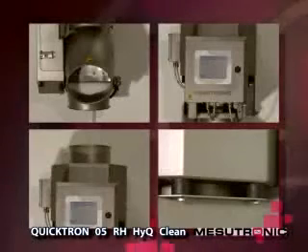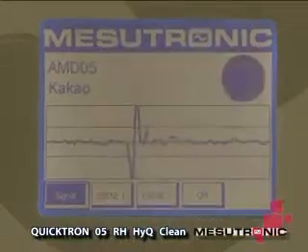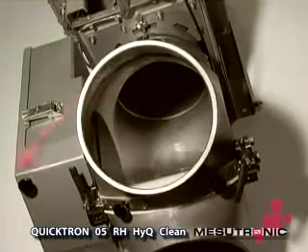A completely encapsulated coil with integrated piping flanges but without a sensing tube. Since this system is immune against electromagnetic interference, we can guarantee a sensitivity of down to 0.4 mm, depending upon detector size.